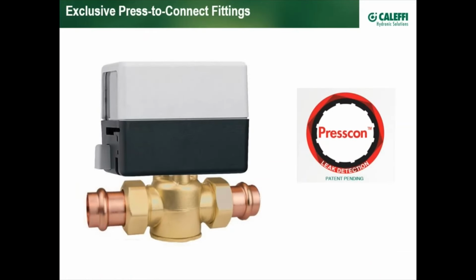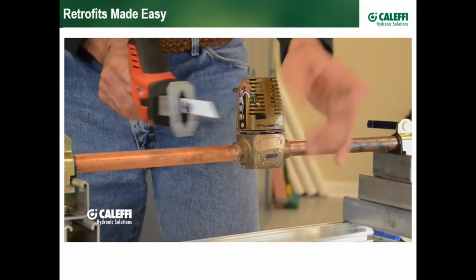But what I wanted to point out are fittings. Unique in the United States, at least as of now, Caleffi has union type compression or press fittings with leak detection capabilities. This is a cross section of this piece right here, showing these little notches. If the contractor leaves the job and forgets about maybe a connection point being compressed when the system is filled, leaking will take place. I'll show that in another slide.